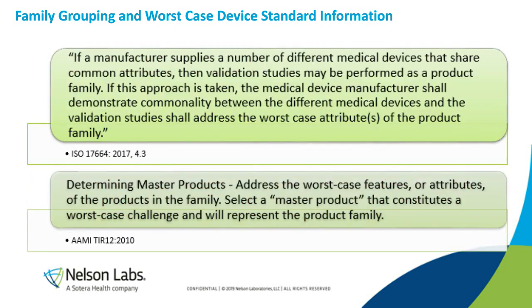To help with this justification, we can reference information in current standards and guidance documents that allow for this rationale. ISO 17664, republished in 2017, Section 4.3 states that if a manufacturer supplies a number of different medical devices that share common attributes, then validation studies may be performed as a product family. If this approach is taken, the medical device manufacturer shall demonstrate commonality between the different medical devices, and the validation studies shall address the worst case attributes of the product family. AAMI TIR 12, published in 2010, helps to define master products by specifying to address the worst case features or attributes of the products in the family. It specifies to select a master product that constitutes a worst case challenge and will represent the product family.